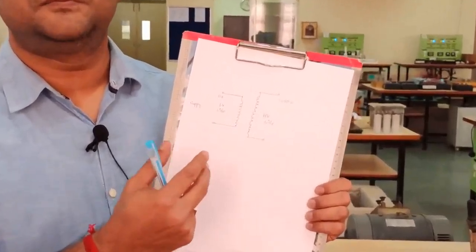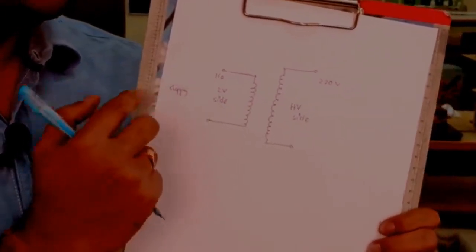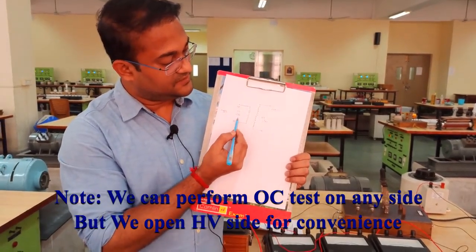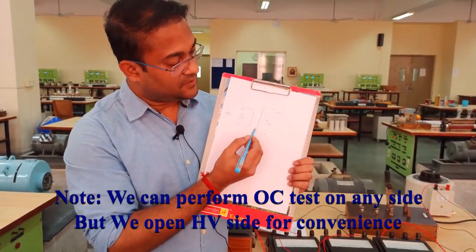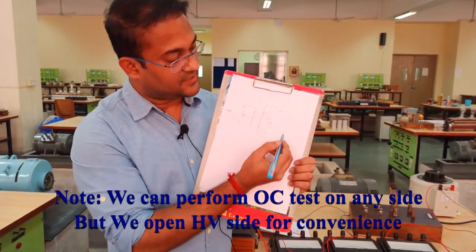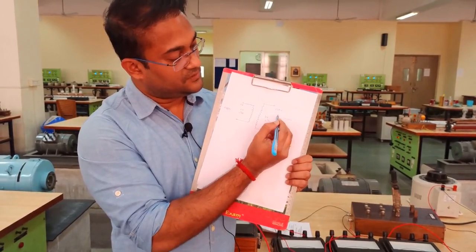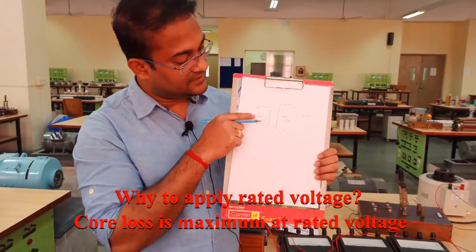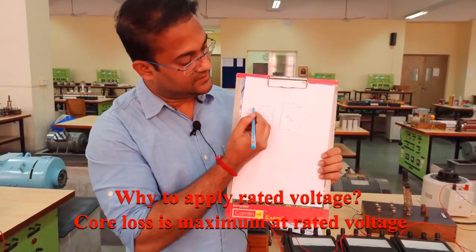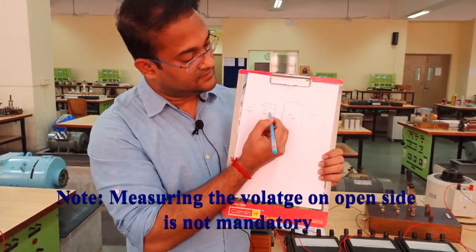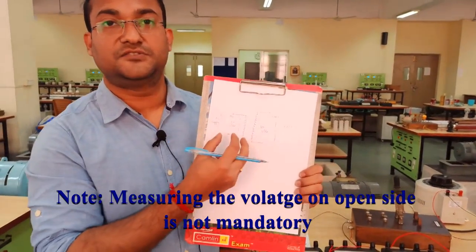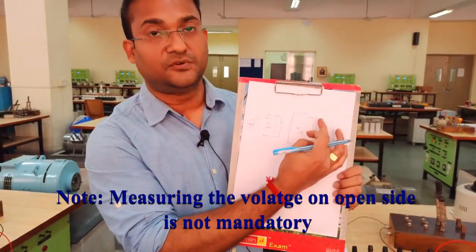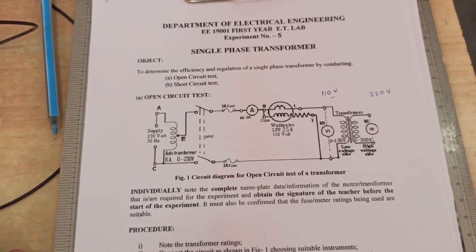To perform the open circuit test, we have to open circuit one side and connect the power supply to the other. There are two sides: the HV side and the LV side. If we perform the test on the high voltage side, we need a power supply and voltmeter rated for 220 volt. But if we perform the open circuit test on the LV side, we only need a 110 volt power supply and 110 volt voltmeter. So the instrument ratings are lower if we connect the power supply on the low voltage side and keep the high voltage side open.